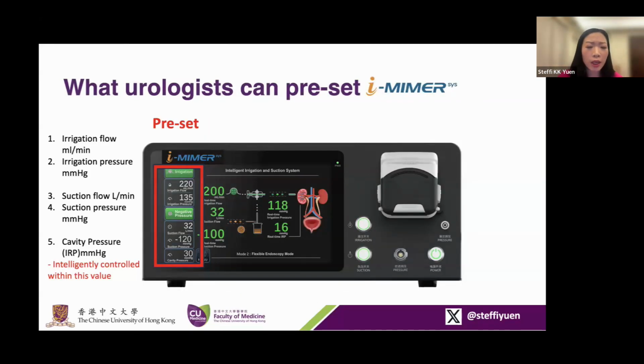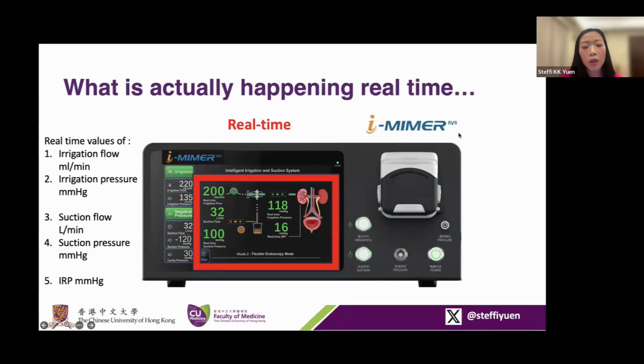Just to navigate you on the interface of the MIMER system, if you look at the interface, the leftmost figures are what you can set. You can set the irrigation pressure, irrigation flow. You can set the negative suction pressure and flow, as well as the cavity pressure, which is the IRP pressure. You can set a maximal threshold, and it will intelligently control within this value. You can look at the real-time pressure when everything is connected, the real-time irrigation flow and pressure, suction flow and pressure, as well as the real-time intrarenal pressure.